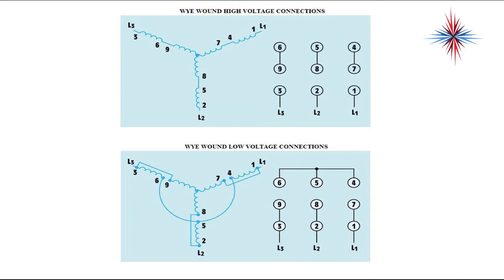So, Y high voltage connections, you would connect your wires to L2, L1, and L3. You would jump together 6 and 9, 7 and 4, and 5 and 8. It will always tell you on the label what wires you jump together. For a Y-wound low voltage connection, you're going to jump together 6 and 9, 8 and 2, 7 and 1, and then you're going to connect 4, 5, and 6 together.